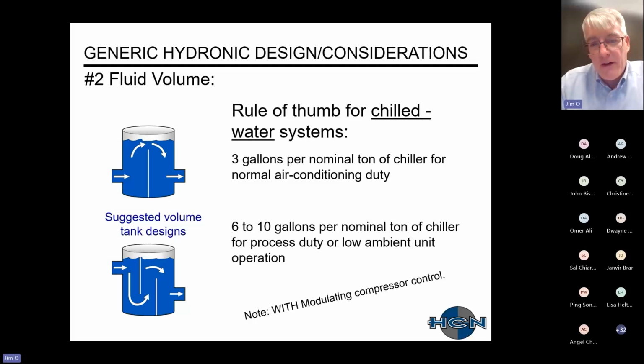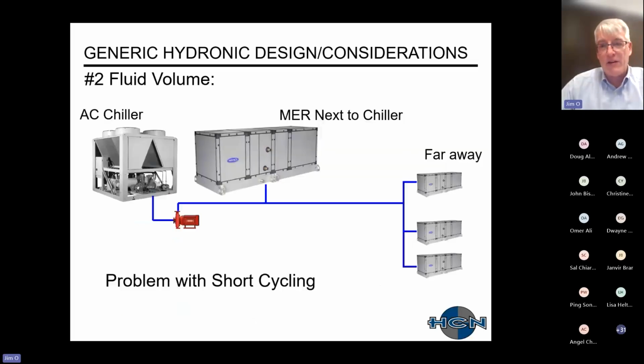One thing with process: with HVAC, your cooling load on a day like this is pretty steady, whereas on a process, we're expecting it to be very intermittent. So the unit is off, and then the manufacturer has a request to turn on their manufacturing equipment, and boom, the chiller's got to come up and running. And then, side note, just check with manufacturers on their recommendations. And also, for any type of equipment, always add as much modulating control as you can: scroll compressors, VFD compressors, et cetera. They seem to be the norm once again today, whereas, dating myself, that was not the case years and years ago. You would add inefficient hot gas bypass.